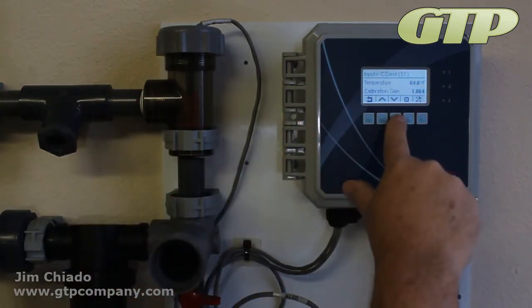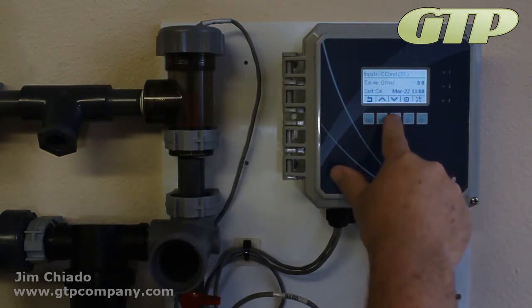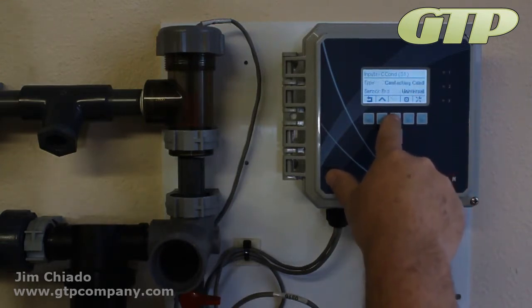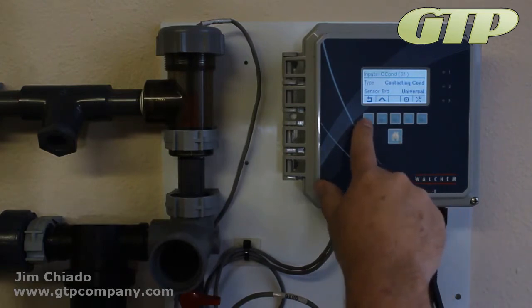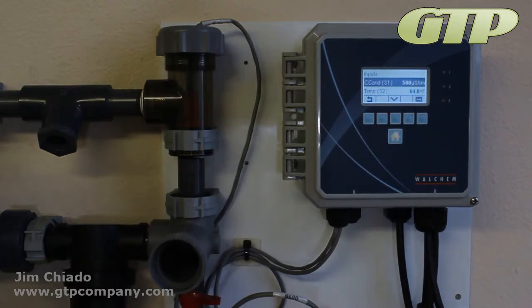The calibration gain is 106, really not much off. Offset 0. Calibration conductivity, and the universal is for the sensor board. But that's basically conductivity. I don't really need to do a 2-point on conductivity, especially on a cooling tower. You're going to keep doing that.